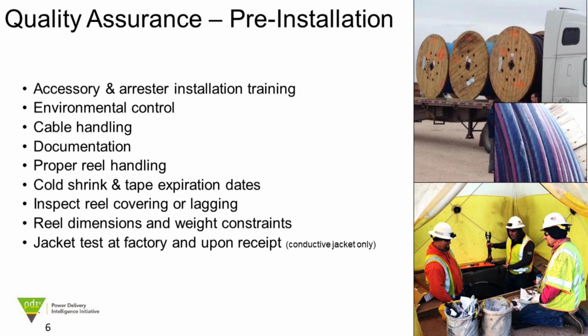Yeah, so after training, we obviously want to make sure that they have proper documentation and handling. Landry has probably some more comments here on this particular slide. But for medium voltage, there isn't much you can do other than checking for, say, shorts in the system, because it doesn't have that conductive jacket, whereas at high voltage or transmission levels, you have a conductive jacket. You can actually make a measurement on the jacket itself to see if there's any significant punctures, which would suggest that maybe the cable itself has been damaged. As far as the joints or terminations, splices or terminations, there's not much you can do until they're installed. They've been factory tested with a power frequency PD test. Then when it's in the field, you're really going to need to wait till it's installed.